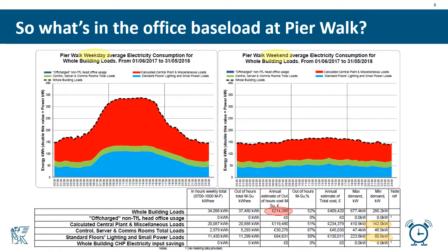When we came to COVID, we thought we'd try and drill down and replicate this chart for this building. Unfortunately, the metering was dead. Half the load, it has a fabulous super logger in the loft, in the roof plant room, and they've been broken. And for the want of £2,000 last year, they didn't sign off on the expenditure. So all we can see from COVID is the total, that incoming fiscal supply. So the black dotted line is what it was just before lockdown, so around about the beginning of March. That's a sample week, and this is a sample week about 5 weeks in, so 11th of April, when we pretty much got it back down to that base load. We've got it a little bit below, in fact, if you looked at the weekend from March time.